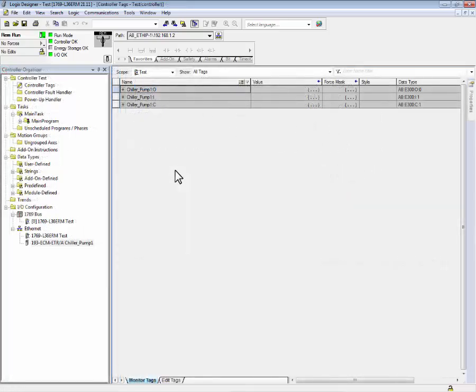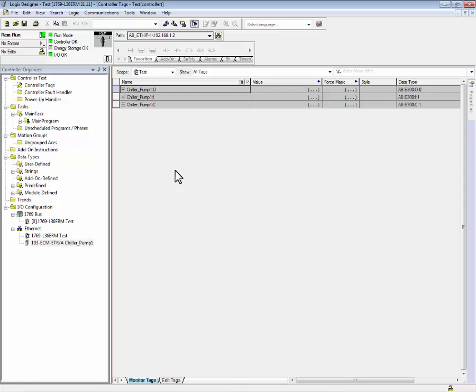Using a device profile makes communications easy with the E300 electronic overload relay and any Rockwell Automation Logix controller. With a simple few mouse clicks, a user can add a device to the Logix controller, configure the device, and it also includes automatic device configuration, in which if a device were to be replaced, the Logix controller would automatically download the configuration data to the new device.